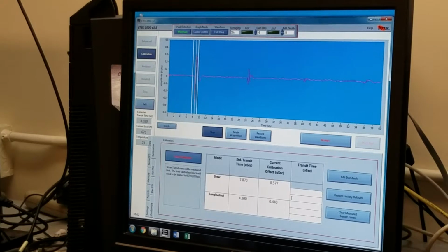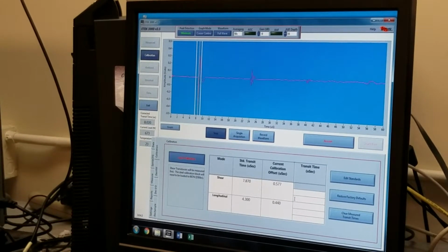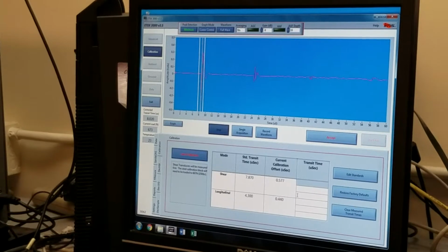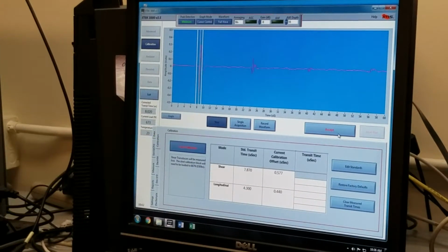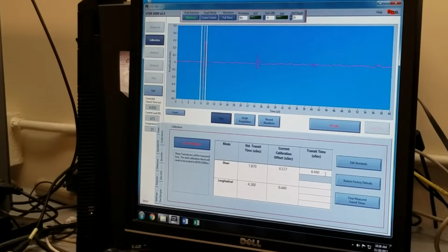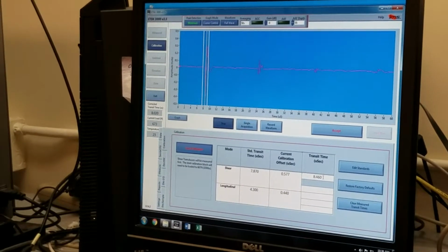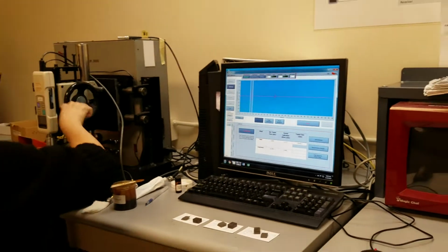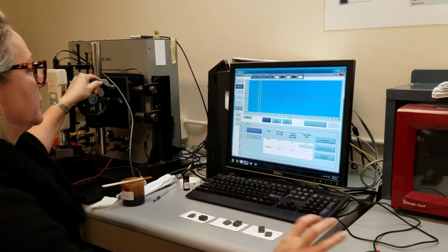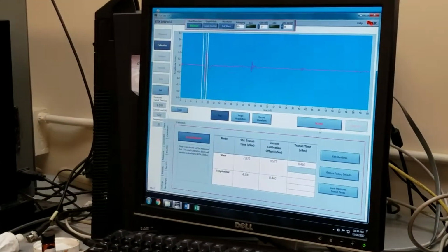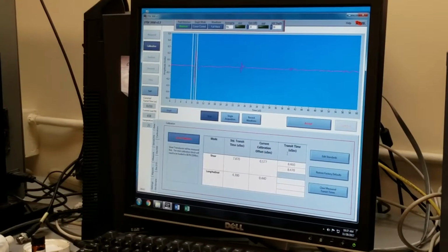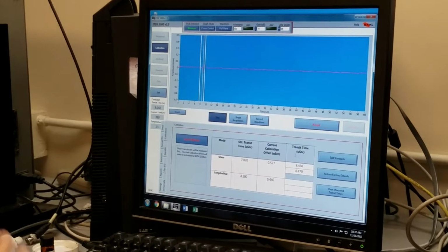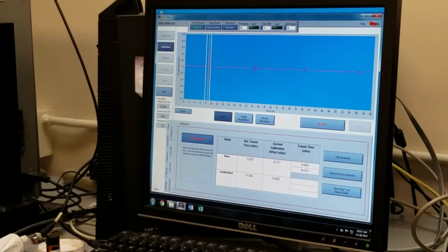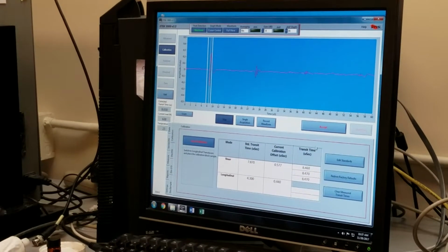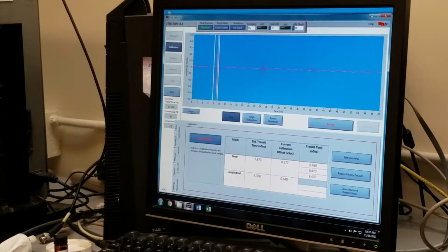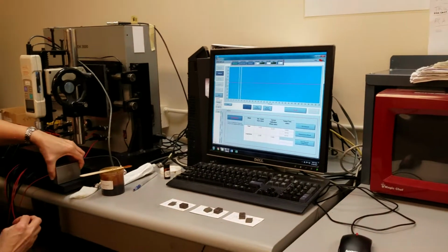Okay. Now that we're on the calibration screen, and I have 700 newtons of load in place, I can click accept, and the transit time is displayed. I'm going to repeat this measurement 3 times to complete the shear wave portion of the calibration. Okay. And at this point, I need to change the transducers.